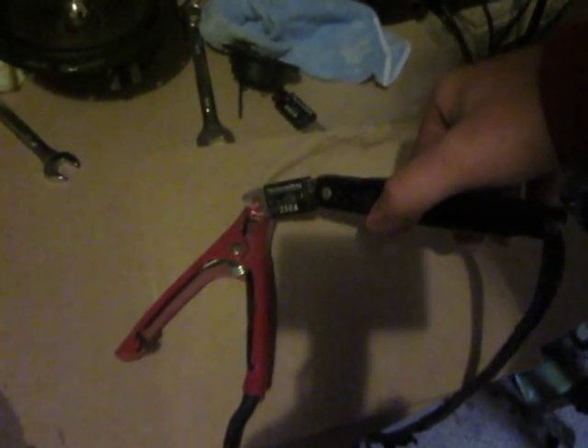Just to point out, I don't think you can see it there, but the actual cables here are smoking. The battery was sitting at 14 volts — we just drained it down to 13 even. And as you can see, the fuse has gotten so hot that it turns red.